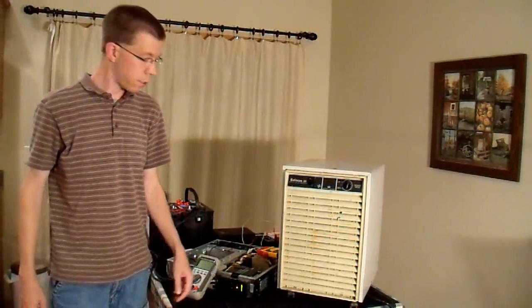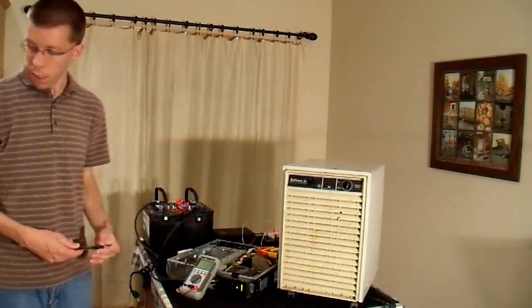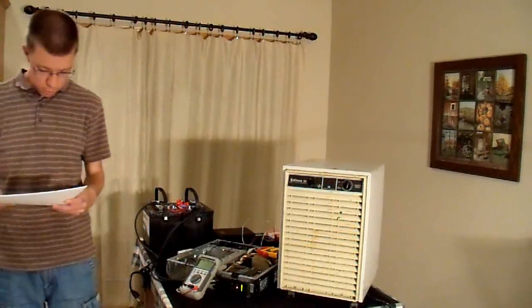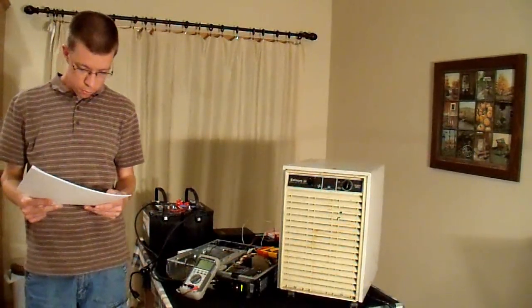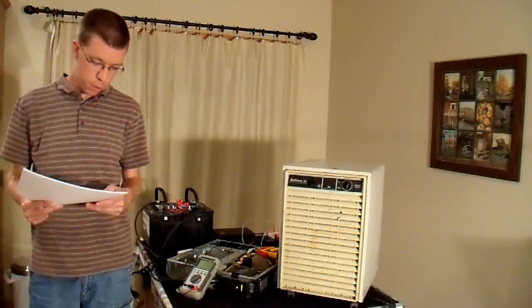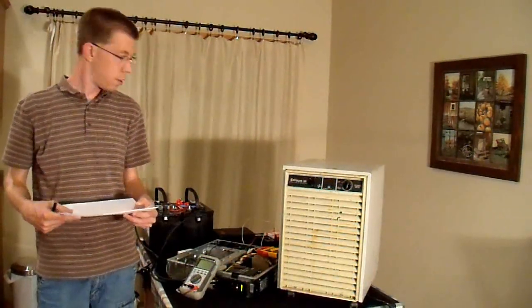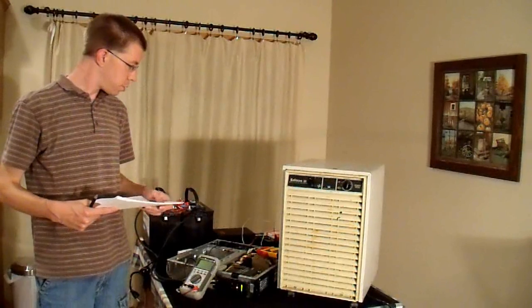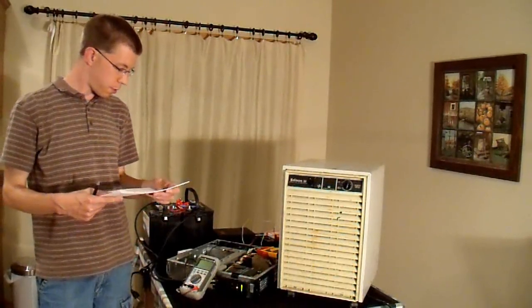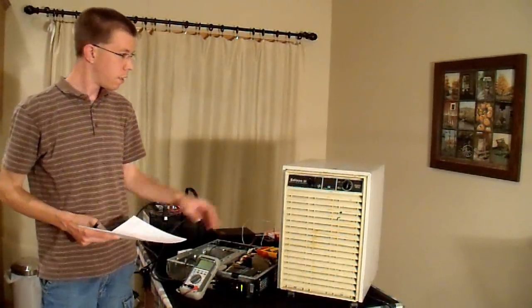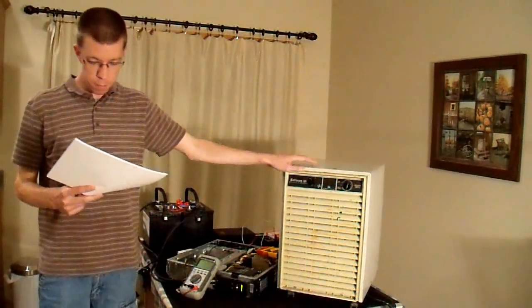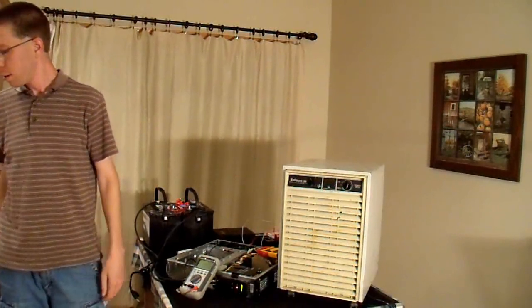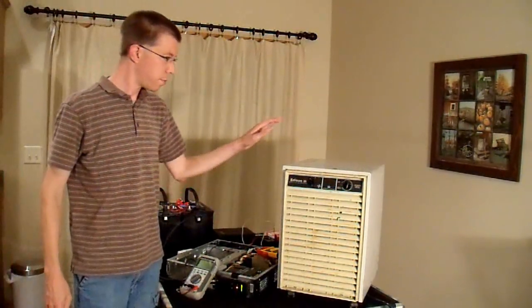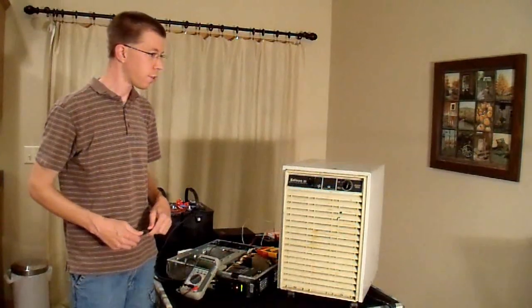That's really not a surprise, but if I take those numbers and do the math on those, 80 volts at 22 amps, I get about 1,760 watts. So that's the surge capability of this unit, somewhere around 1,700 watts. And the dehumidifier, when plugged into the wall, has a surge draw of 3,500 watts. And the reason that the battery is lower, when it's running off a battery, the draw is lower, is because the voltage sagged to 80 volts.